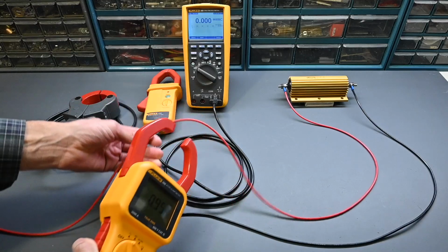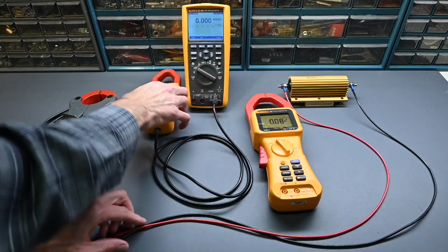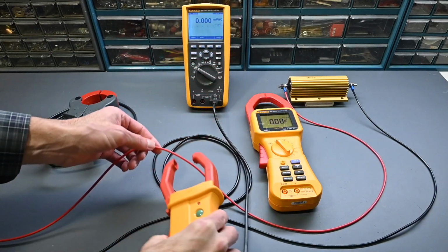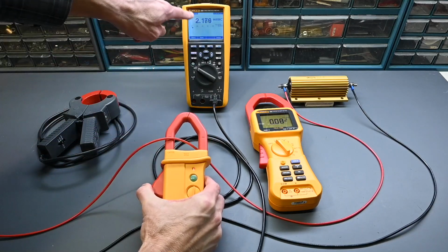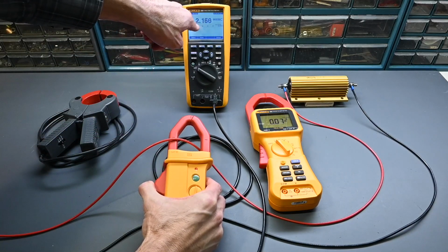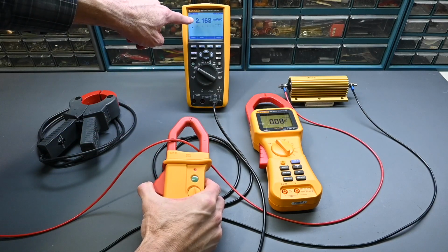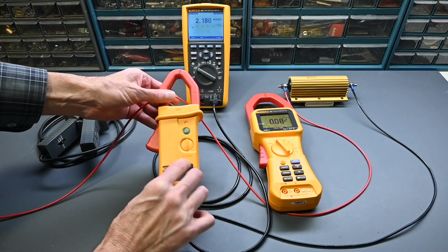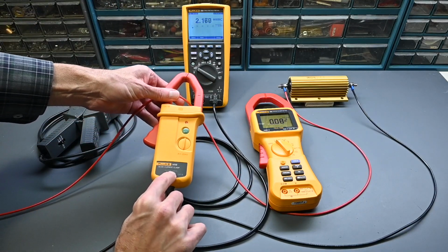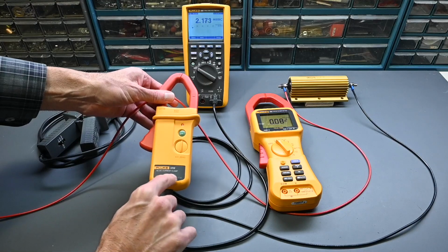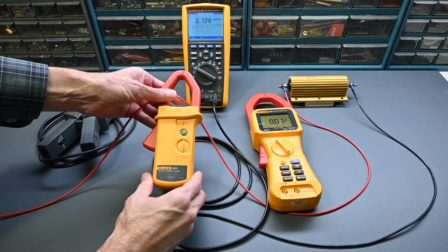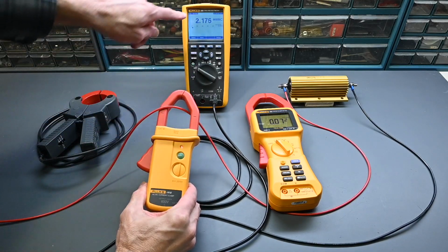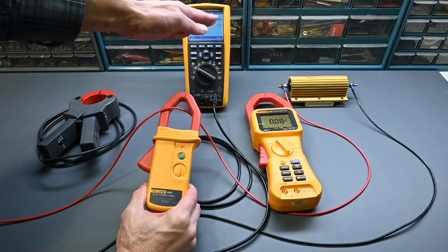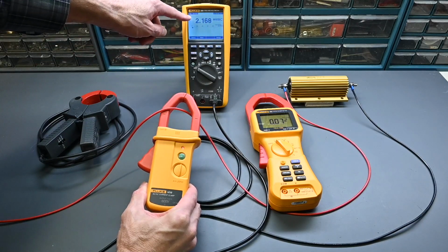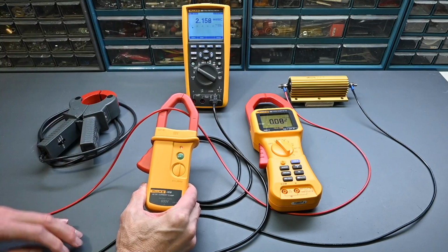Wire just goes right through the current clamp and you get the reading. And if I go like this, clamp right here, you can see it says 2 point and some change, but millivolts AC. So on this current clamp, the output is rated 1 millivolt per amp. Knowing that that's the ratio, you just use that factor when you're taking the reading here. Even though this is millivolts AC, you're reading it as amps. So 2 millivolts means 2 amps.